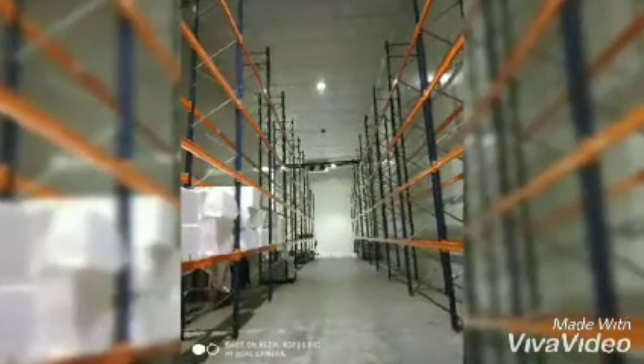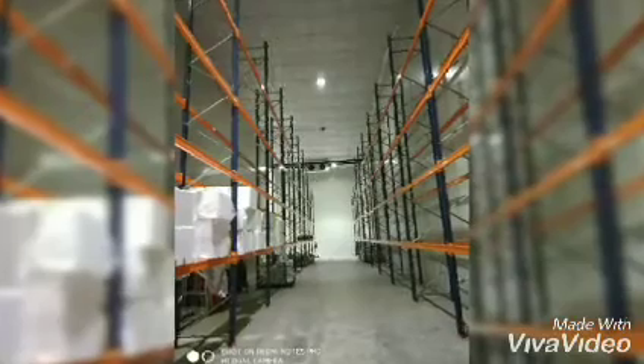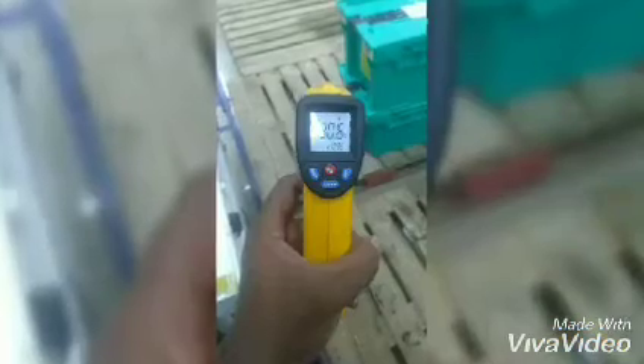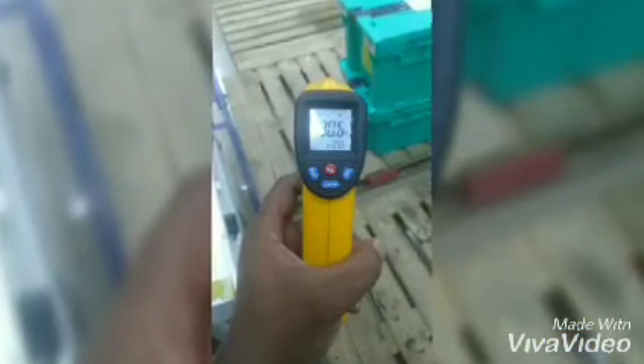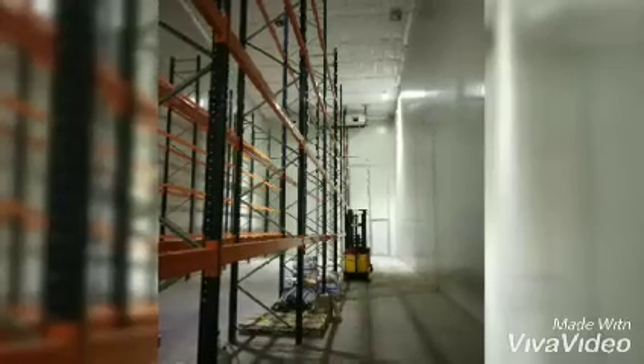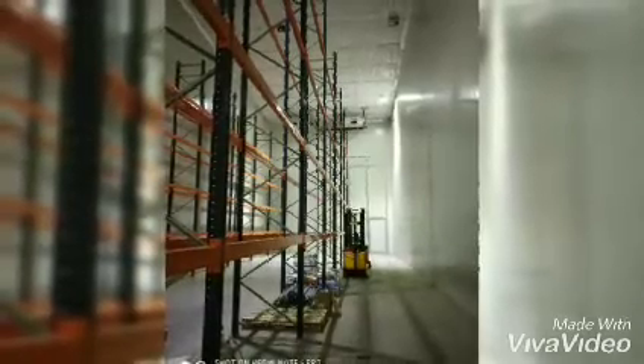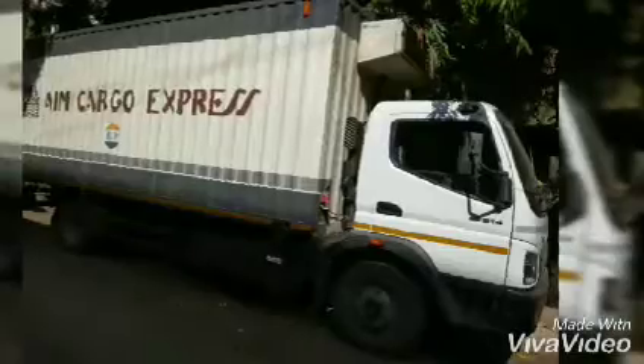Also, on the basis of the OQ and PQ cycle tests, hot spots, cold spots and mean kinetic temperature are identified based on the data extracted from each and every data logger, and these spots are pointed out diagrammatically in the storage area so clients can keep their critical products accordingly.